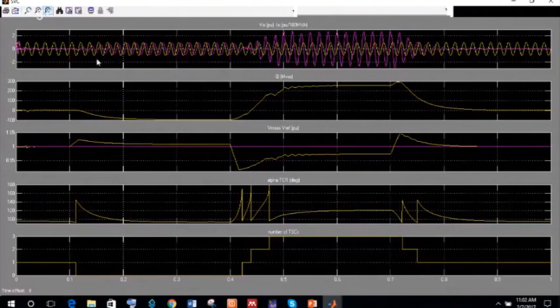So as per the programmable voltage source, the voltage is increased at 0.1. This yellow line indicates the voltage output of the programmable voltage source, which is higher than the reference. This indicates the reference line. So when the voltage rises, the reactor should absorb the power. So here this is alpha, that is for the reactor, that is the thyristor controlled reactor. So alpha is near 144, like that.